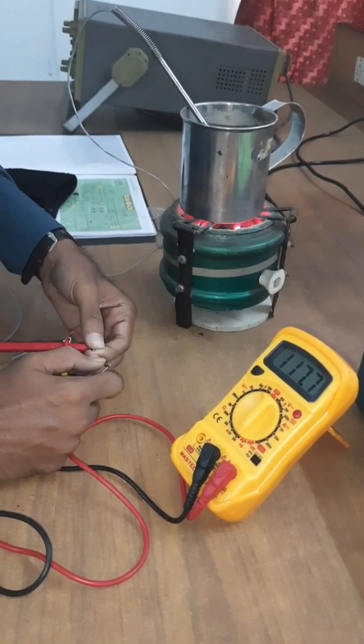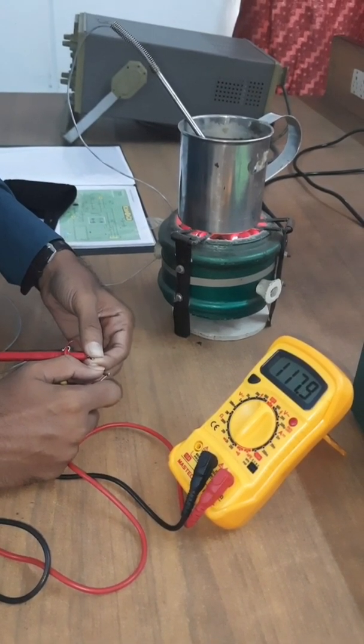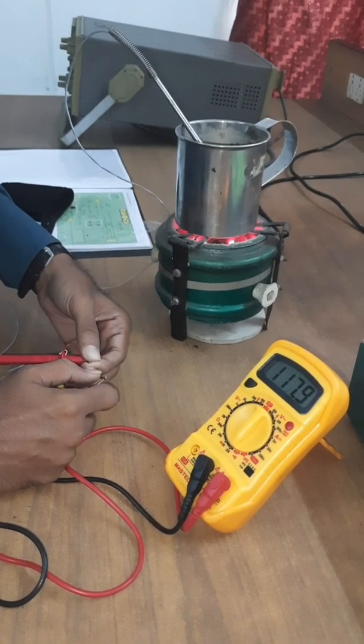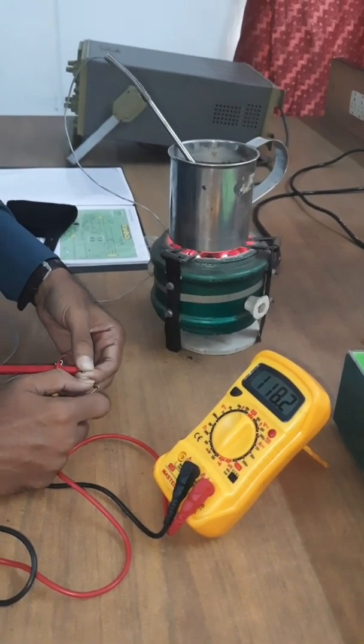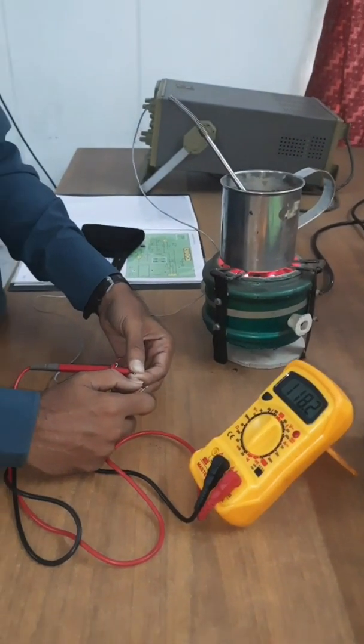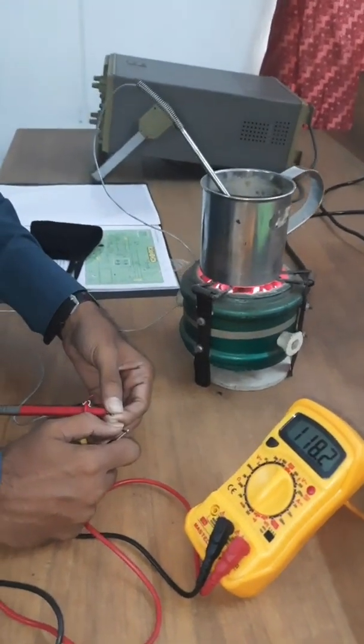I hope you get the picture that from 116.7, the resistance has increased to 117 point, currently it's 118. This demonstrates that as the temperature of the particular process increases, the resistance of the RTD will also increase.